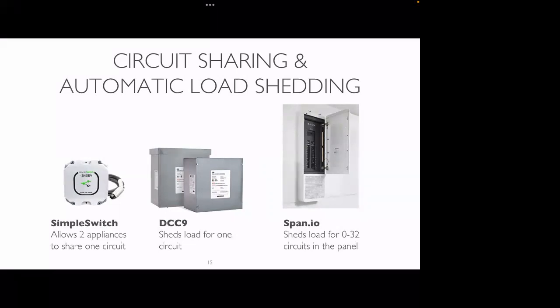That surge of usage might be caused by something like a tankless electric resistance water heater, which tries to heat the water at the same time you're using it, drawing a lot of power. If you had one of those on your panel, you might need one of these load circuit sharing or circuit pausing devices that would pause your car charger while you were showering, then let it back on when there was more space on the panel.